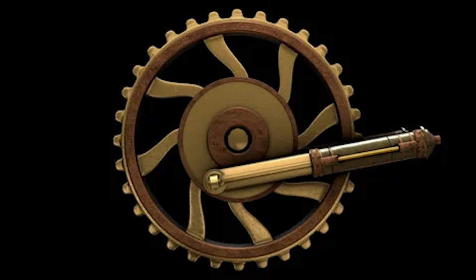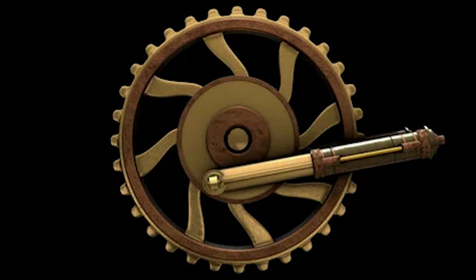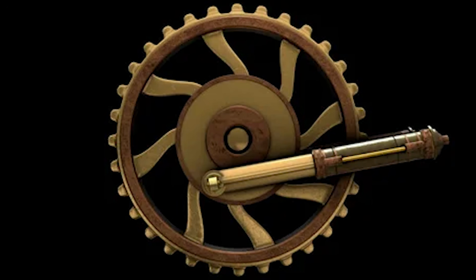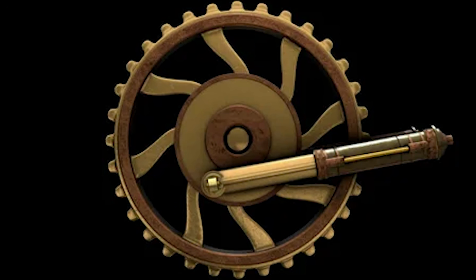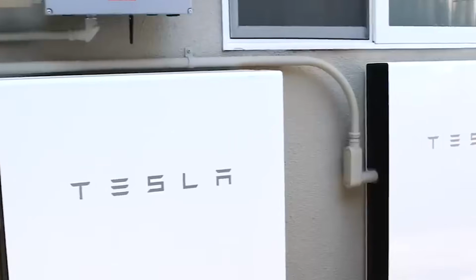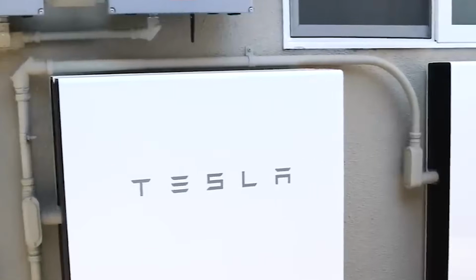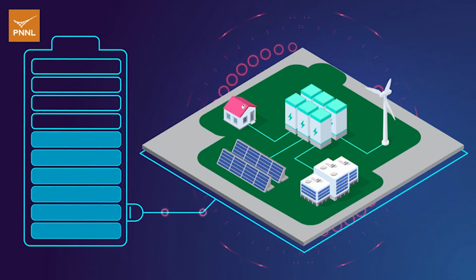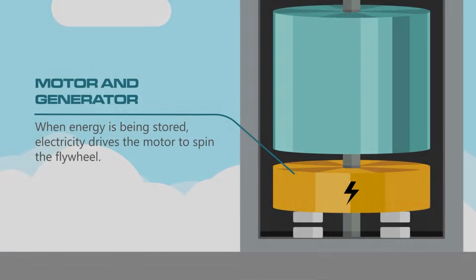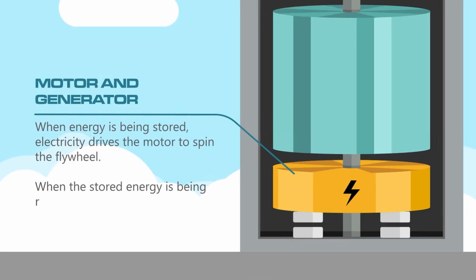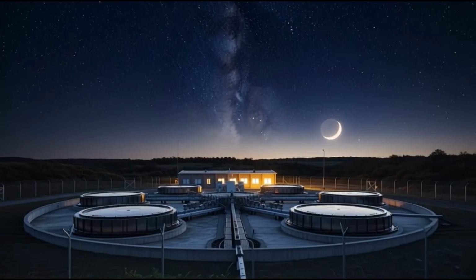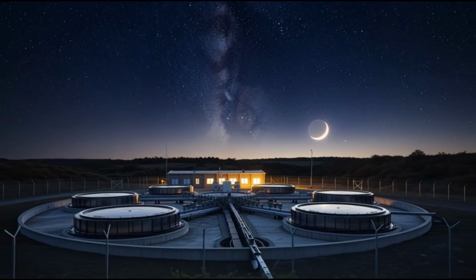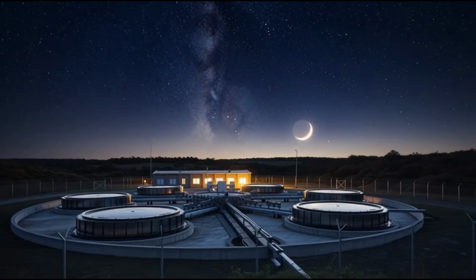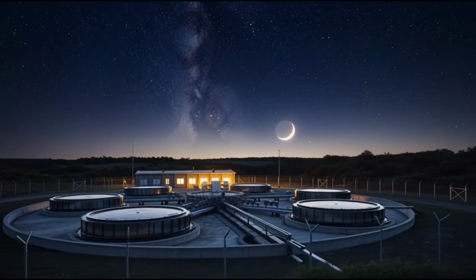A flywheel is not a chemical battery. Its failure modes are completely different. Its thermal profile is completely different. Its degradation mode, which is effectively non-existent, does not map to any test protocol in the standard. Getting a flywheel certified under a framework built for chemical batteries is like getting a sailboat rated under powerboat engine emission standards. The testing categories do not apply.